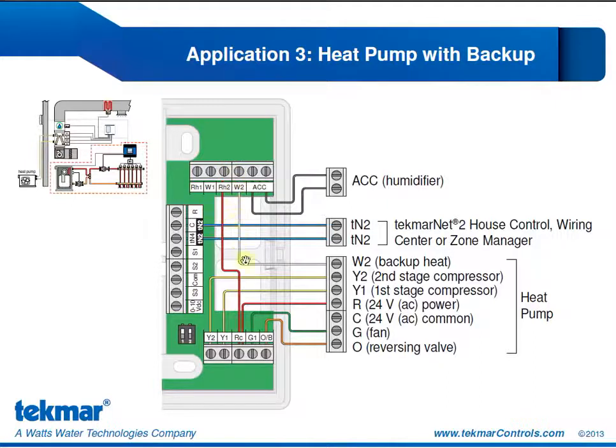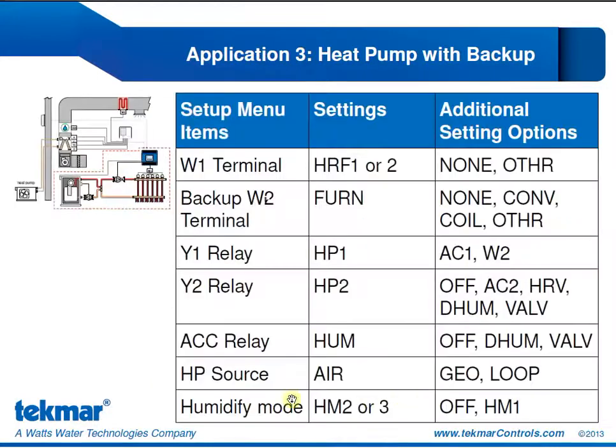So let's trace some of these wires. We have power from the heat pump coming in. We're bringing that up to our RH2, which is connected to W2, and coming over to the backup heat. R is also powering the Y1 and the Y2, as well as the fan, and we will use the O when we want to switch over to cooling mode.